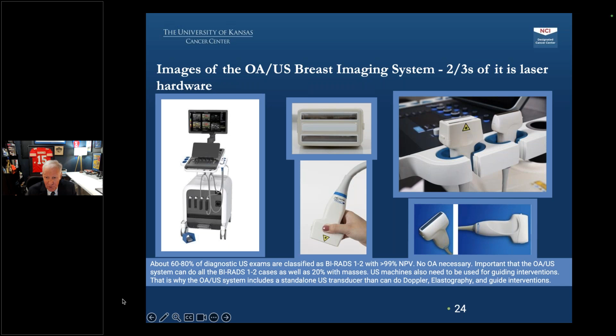So this machine also functions just like a standard high-resolution ultrasound machine, with the advantage of further interrogation with OA when it becomes necessary. Both probes work in duplex mode, meaning with the OA probe, one can fuse real-time ultrasound with Doppler, or real-time ultrasound with elastography, or real-time ultrasound with OA, but not in triplex mode.